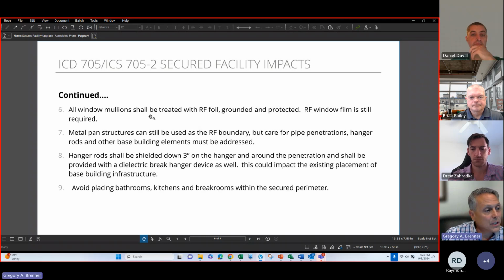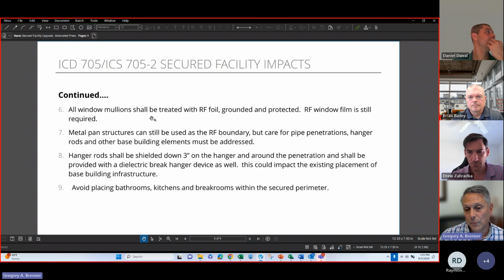Pan structures can still be used as an RF boundary, but you have to care for pipe penetrations, hanger rods, and other base building elements. So again, we can use the pan structure for the ceiling above, but all the penetrations through it now have to be cared for with RF mitigation — often you're doing some foil up onto the pan as well. Depending on the AO, some will let us use that pan grounded; others say no, they want the RF foil for continuity overall.